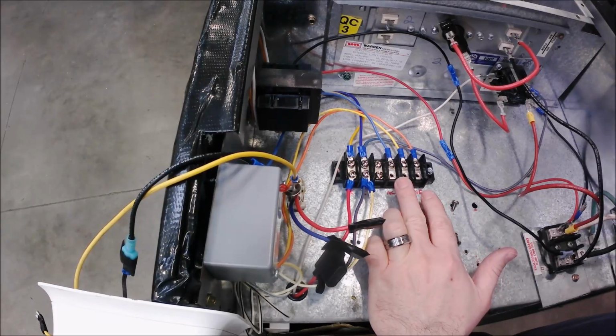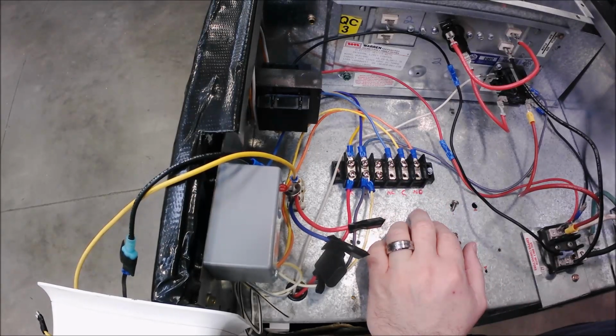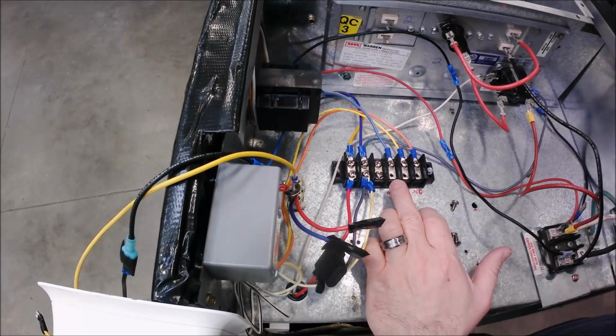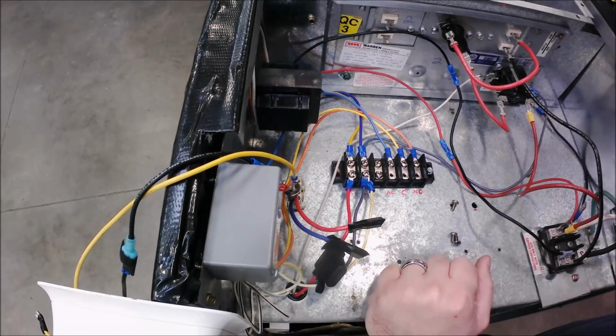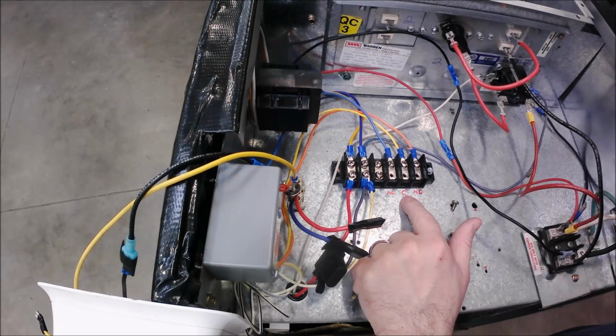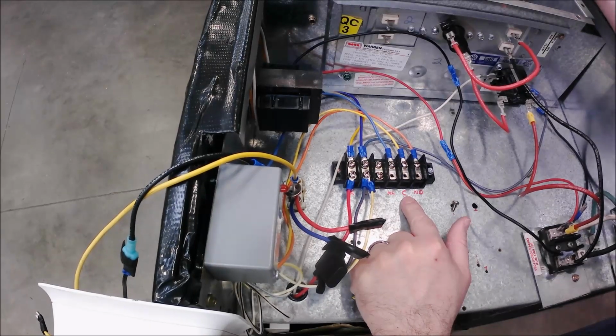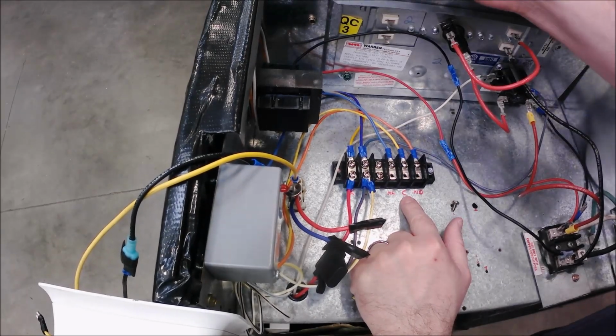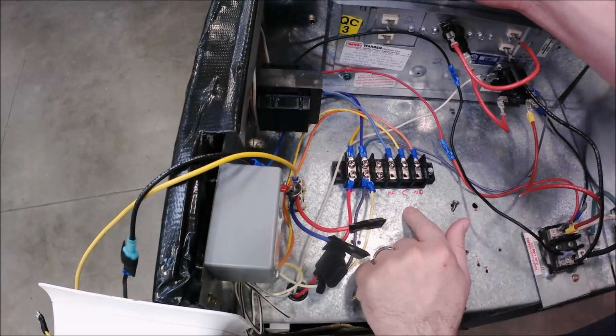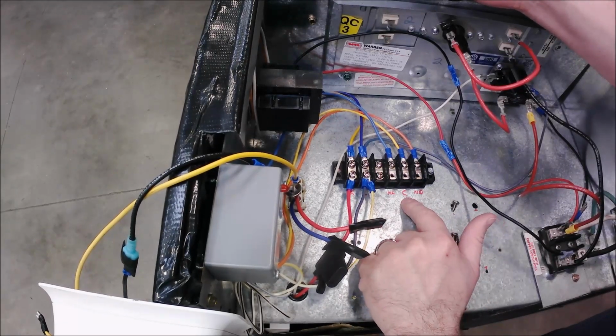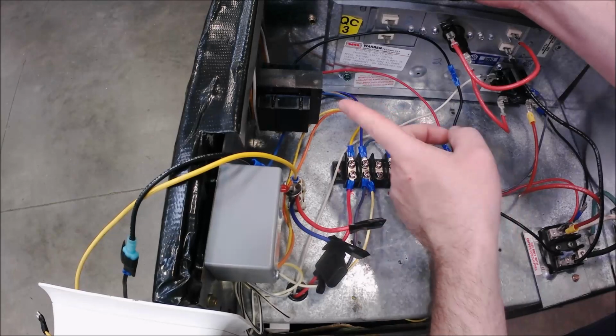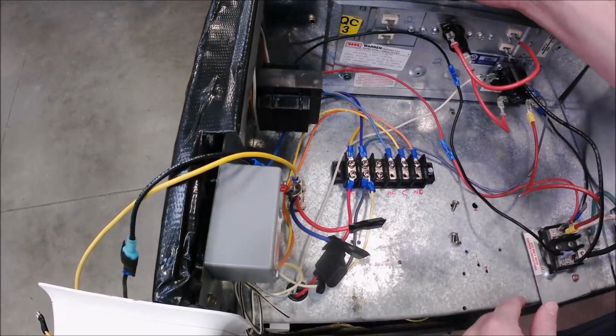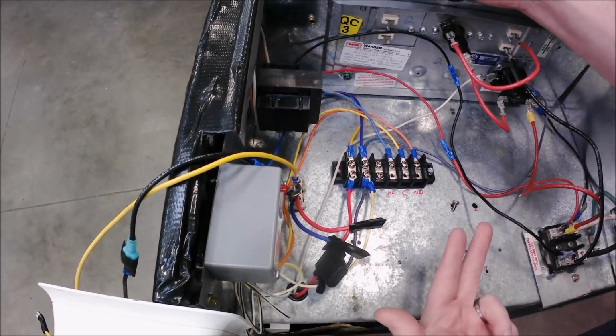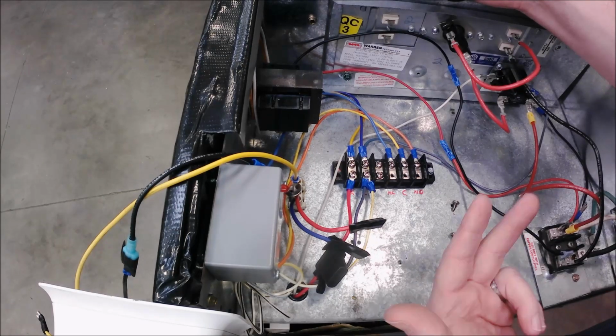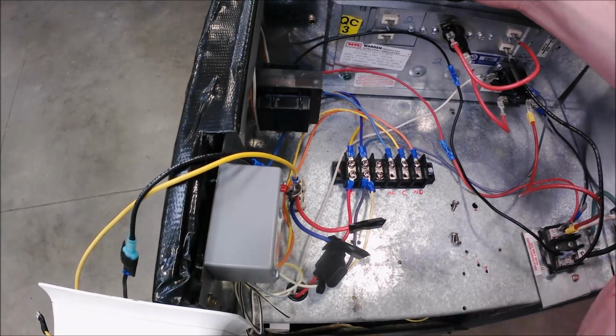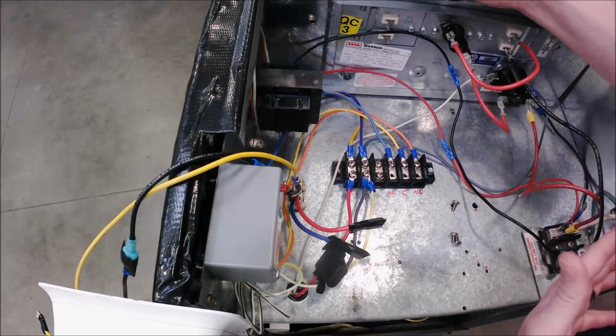What we're looking at now is connecting the fan motor to it. So what I'm going to do here is common. Alright, there's so many commons we use in especially residential heating and air. We have a common for relay and switch situations. We have a common for the 24-volt side of our transformer. We have a common on a PSC motor, one of the 3 terminals. We have a common on a capacitor. I mean, it's a bunch of different commons. You have to know when to apply it.